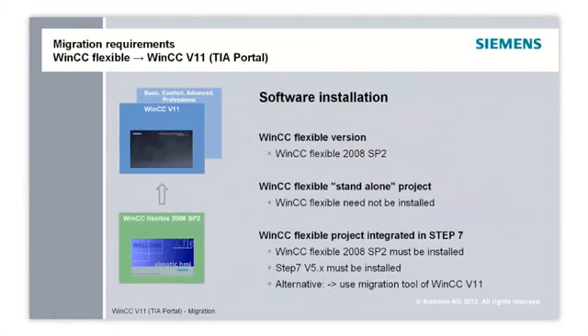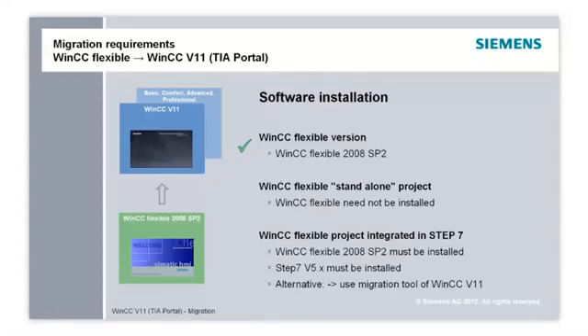Which software requirements apply for the migration? Projects created with WinCC Flexible 2008 Service Pack 2 can be migrated to WinCC version 11. When using older or later versions of WinCC Flexible, please generate a backup of the configuration, then open it with WinCC Flexible 2008 Service Pack 2 or Service Pack 3 and save the configuration as WinCC Flexible 2008 Service Pack 2.